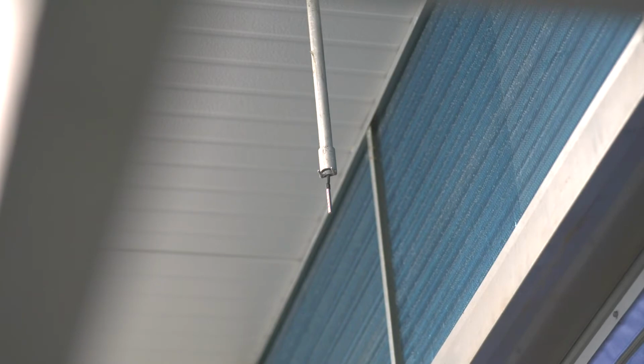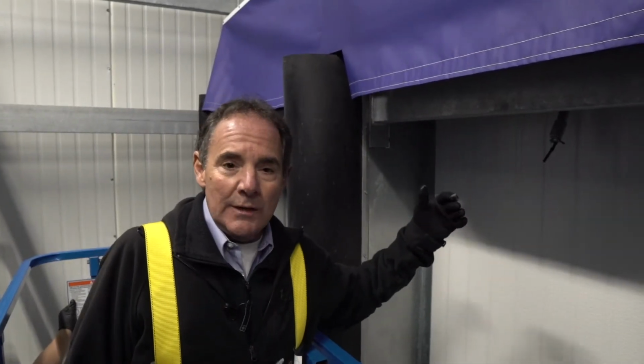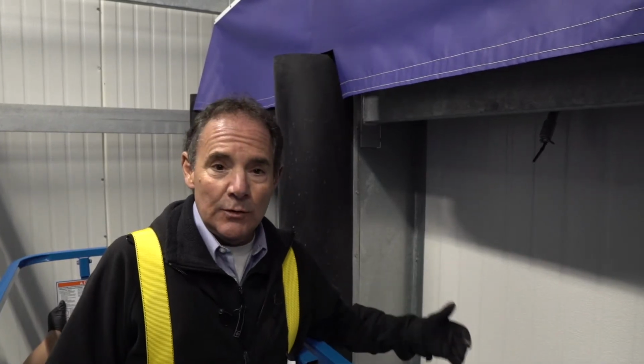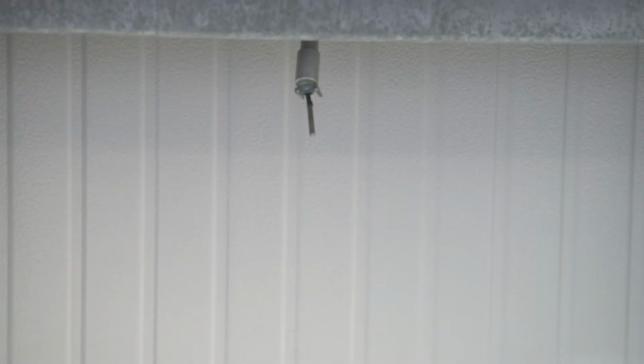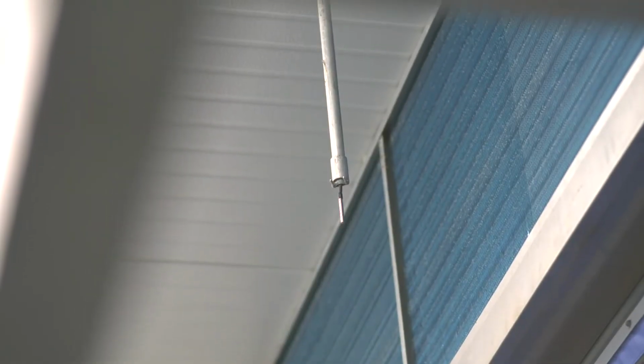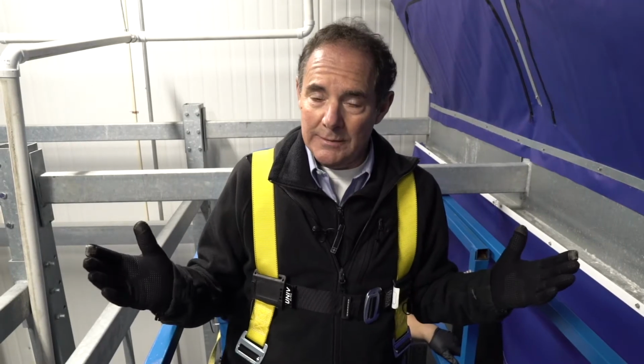There are temperature sensors located on both sides of the evaporator. This is the return air sensor. It measures the air temperature prior to it going back through the cooling coils. This is the discharge air sensor. It works in conjunction with the pulp probes to deliver temperature-controlled air throughout the entire room. A single-wide room has a set of sensors on one side, while a double-wide room has a set of sensors on both sides.